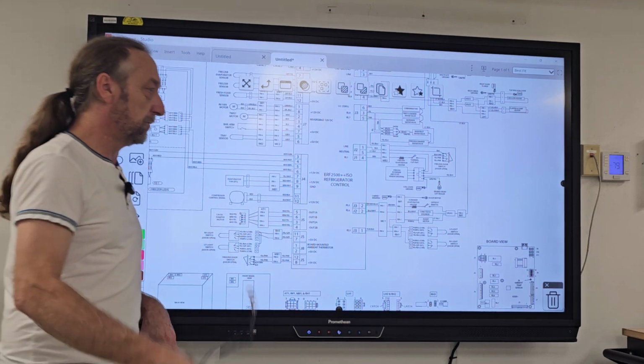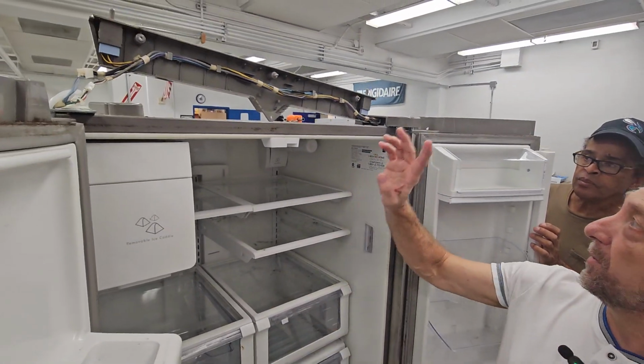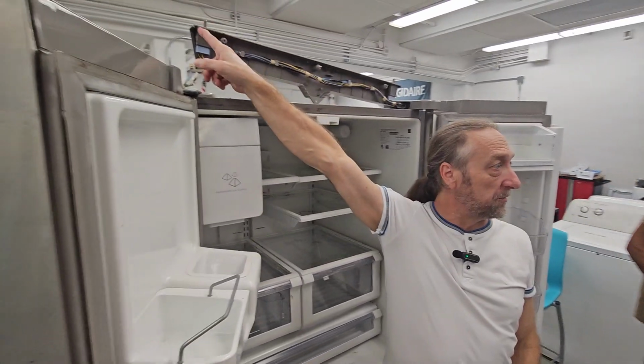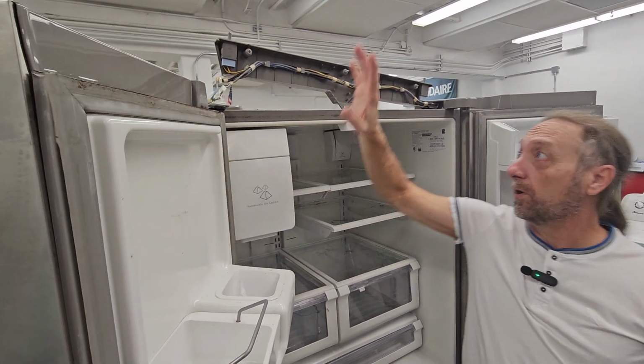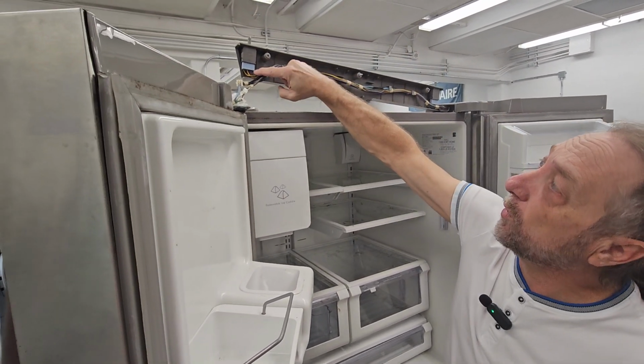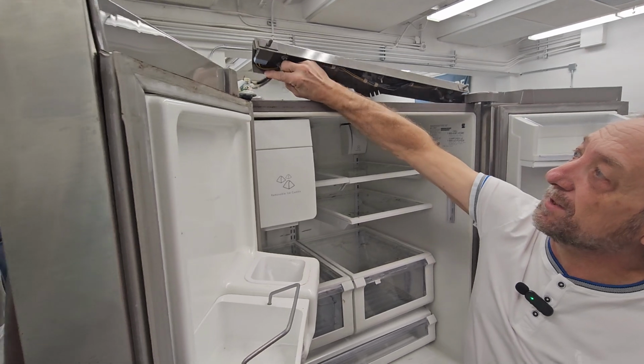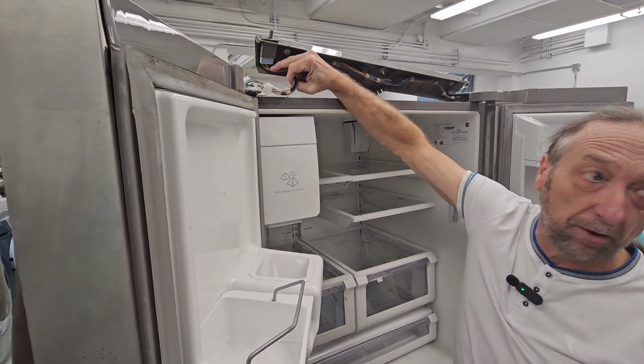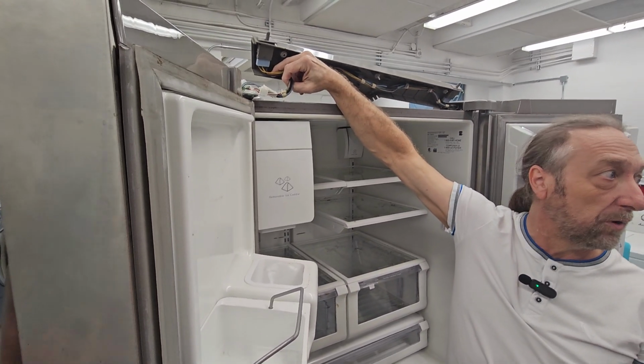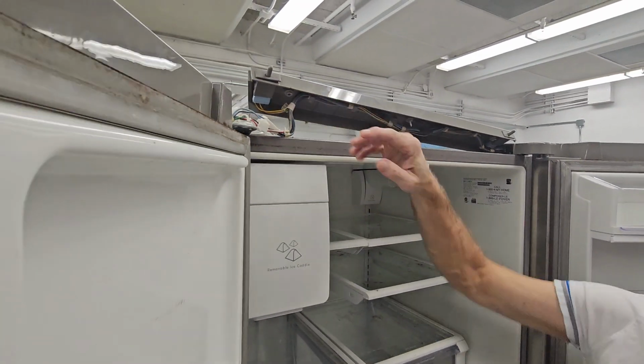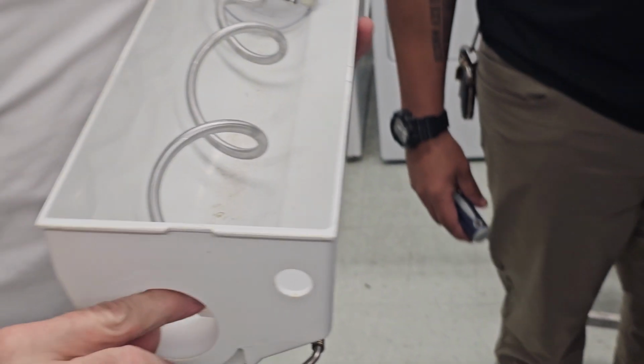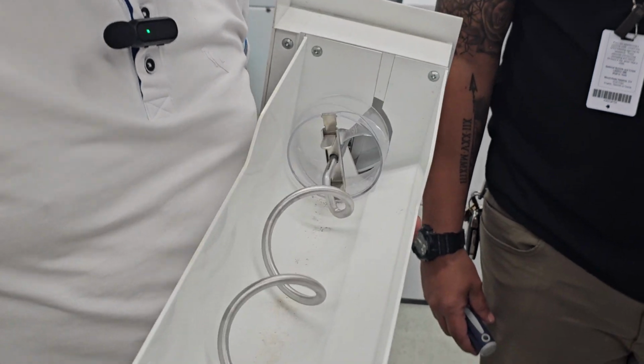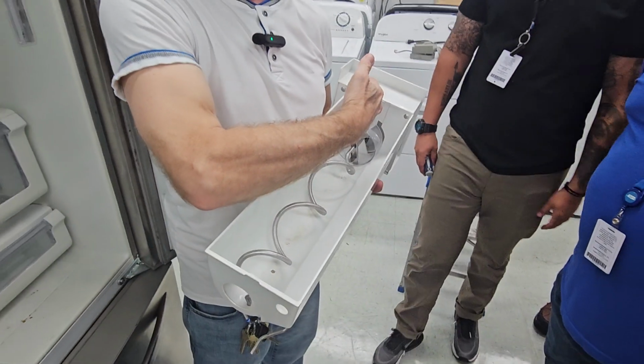I'll pause that for a second. We'll go out. All right, remember I told you there's only two light switches here, one for the left door and one for the right door. But notice there's 4 wires on there. So I don't have the diagram in front of me, but 2 of those wires are low voltage and the other 2 are AC volts. The auger motor, we look inside of this piece here, this is the auger. So when the motor turns, it pushes the ice this way and pushes the ice out the door.